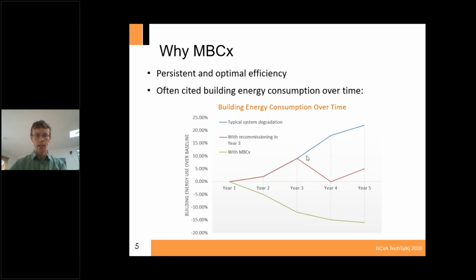As you can see, after you've started your building—let's say this is new construction—and you've baselined your energy use, over time this blue line gradually rises up over the years due to system degradation. Humidity sensors need to be calibrated within 2 to 3 years at the latest. Make sure your economizer modes are still working properly, and that actuators and dampers aren't stuck. If you aren't doing that, you aren't really maintaining your building properly, and you're going to have an increase in energy use over time.